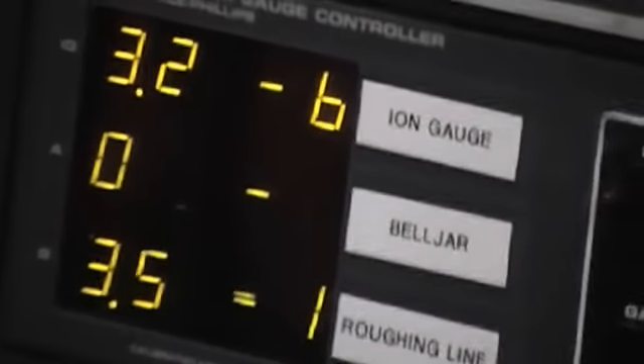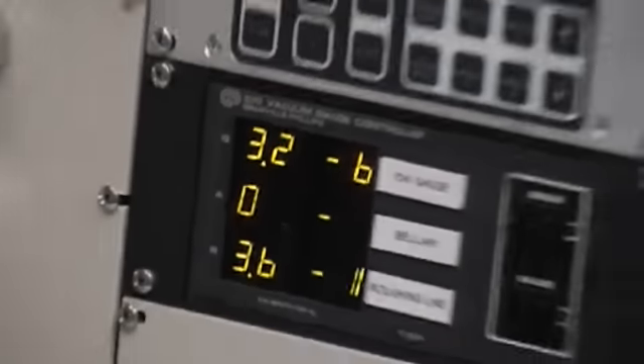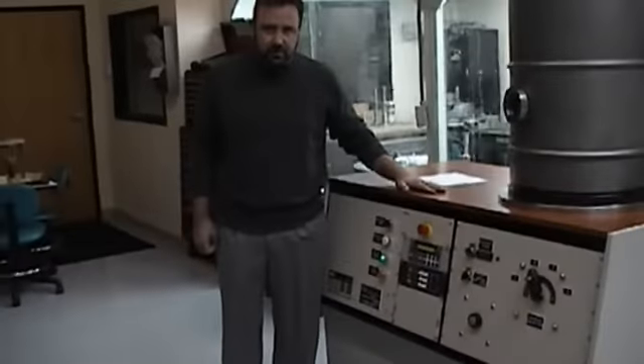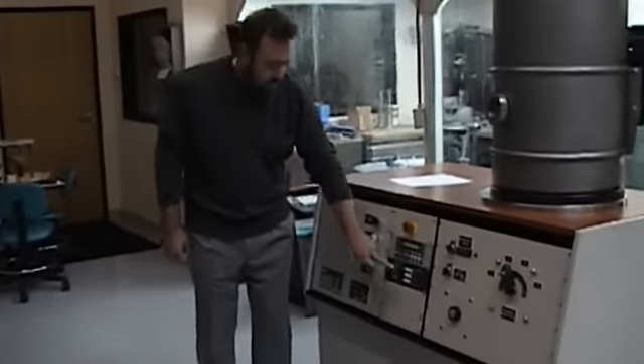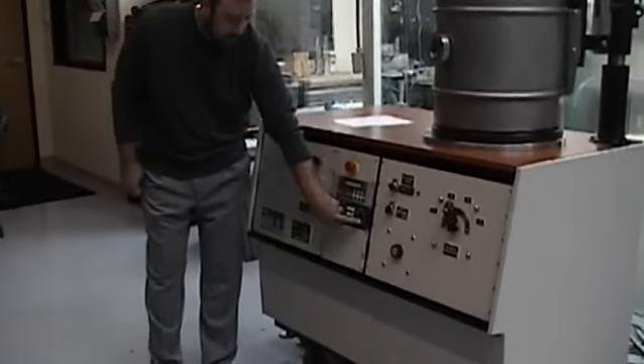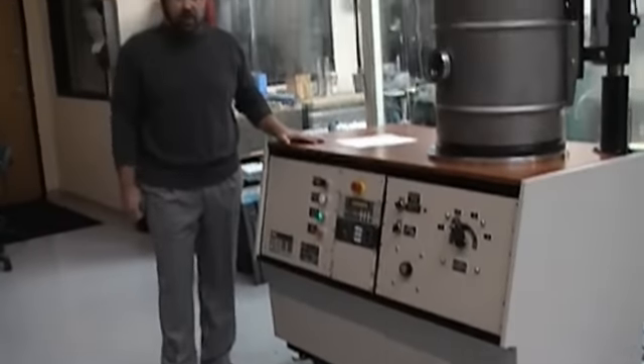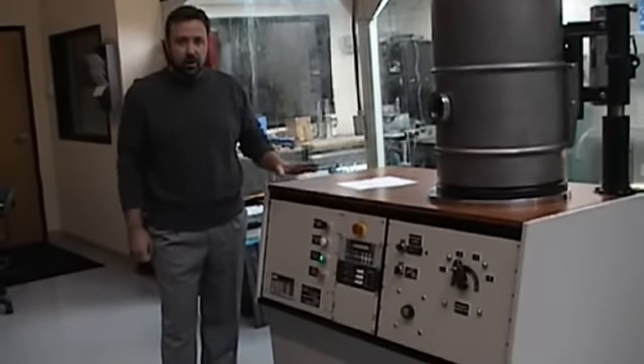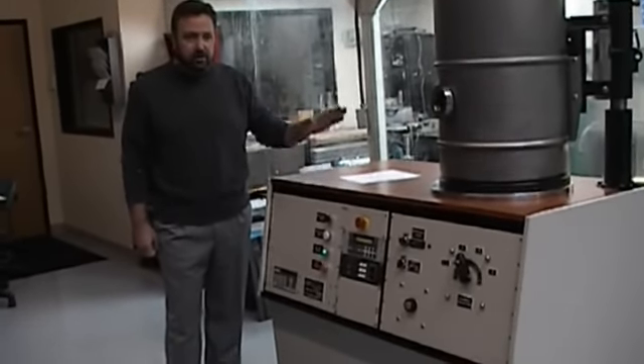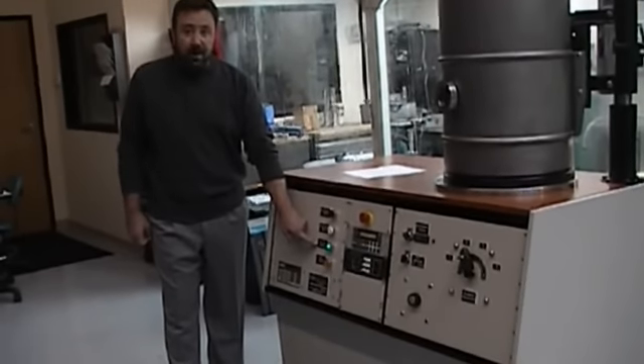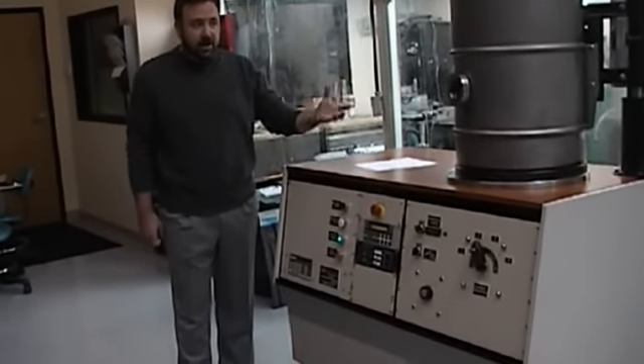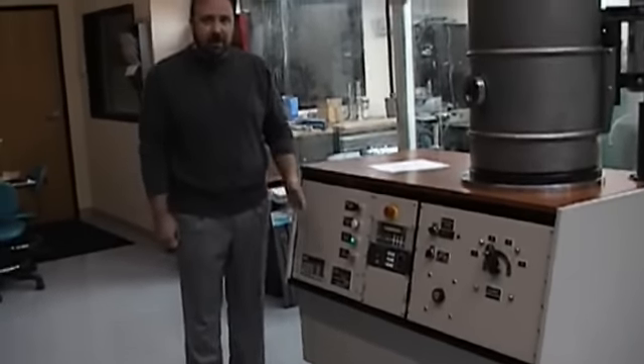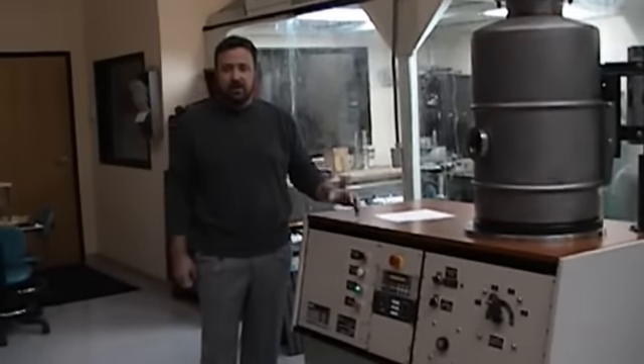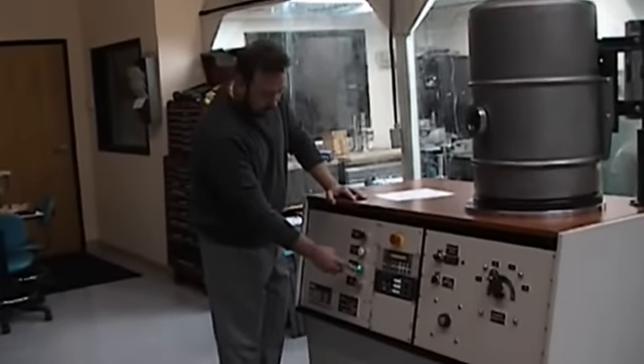Previously, we operated this machine into the 7 range, which it would shortly get to if we allowed it to pump for a lot longer. But we've done some depositions since then. So I'm going to go ahead and turn off the ion gauge. You want to turn off the ion gauge as soon as you shut the high vacuum valve. That's to protect from inadvertently opening up the vent valve while the hot ion gauge is running.